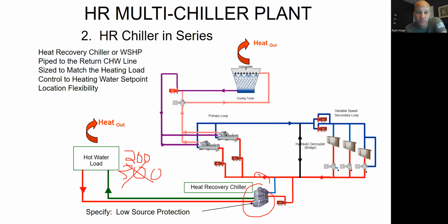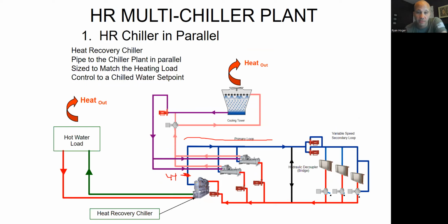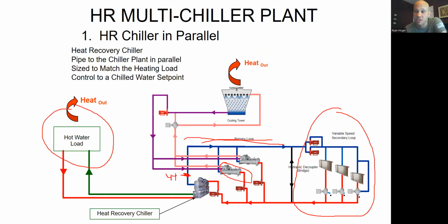In this case, if this load gets dropped down, this guy would also have to ramp down. But now the problem is, hey, this might have been my only source of cooling running for this guy. Now somebody else has to kick on to make up the difference, assuming I still have the cooling demand. This doesn't happen a lot because if your heating demand is lower for the building, meaning you're using less domestic water and stuff like that, that probably means there's less people there, which means you need less cooling. So they usually go up and down together for these simultaneous loads, but not always.